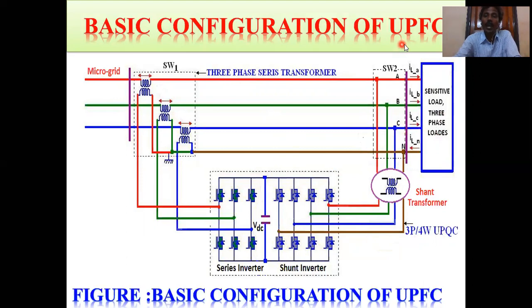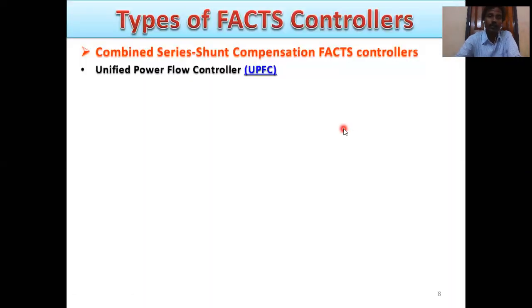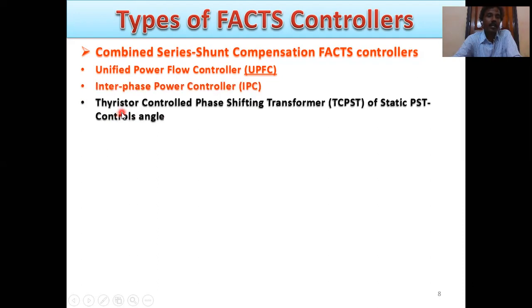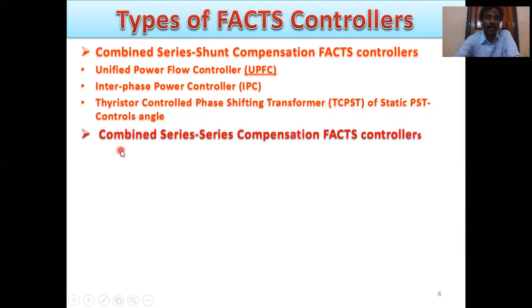This is the UPFC configuration. At the same time, series control on this side and shunt control on this side. That means it injects voltage on this side and injects current on this side. Active and reactive power are both controlled. Also harmonics control. Inter-phase power controller, IPC. Other types: thyristor controlled phase shifting transformer, TCPST, or static phase shifting transformer, controls the angle.